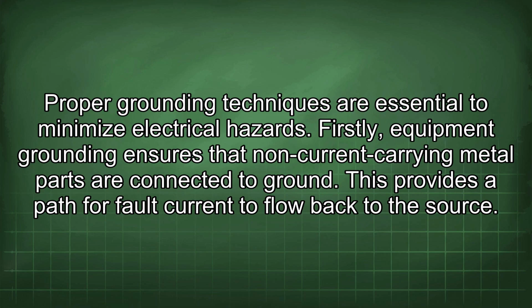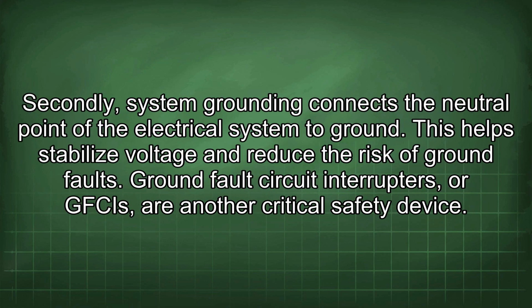Proper grounding techniques are essential to minimize electrical hazards. Firstly, equipment grounding ensures that non-current carrying metal parts are connected to ground. This provides a path for fault current to flow back to the source. Secondly, system grounding connects the neutral point of the electrical system to ground. This helps stabilize voltage and reduce the risk of ground faults.